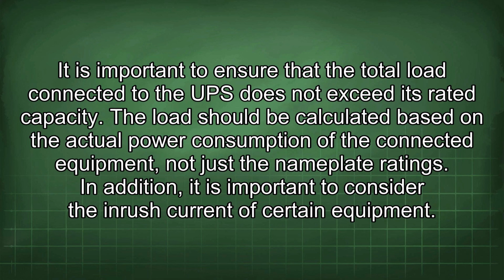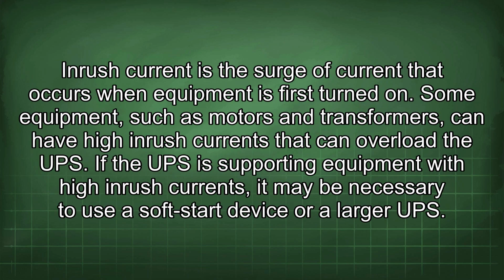In addition, it is important to consider the inrush current of certain equipment. Inrush current is the surge of current that occurs when equipment is first turned on. Some equipment, such as motors and transformers, can have high inrush currents that can overload the UPS.